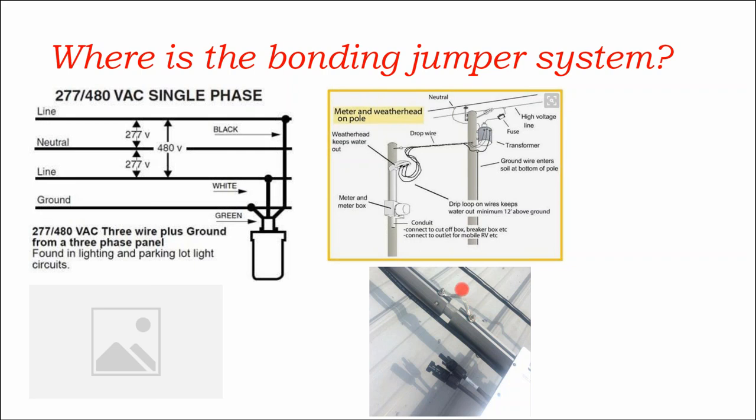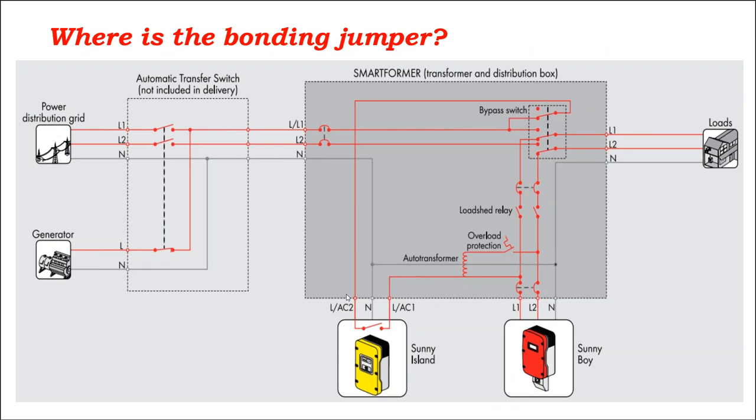Or here is a listed component that ensures that this piece of rail and that piece of rail get grounded. And maybe that splice is a listed grounding component. Usually it's not. Usually it's different. So just because you're screwing some metal into some other metal does not mean you're officially, in the eyes of code, bonding the two pieces together. What code is going to try and do is make sure that whatever is being considered the ground path will actually be the ground path.